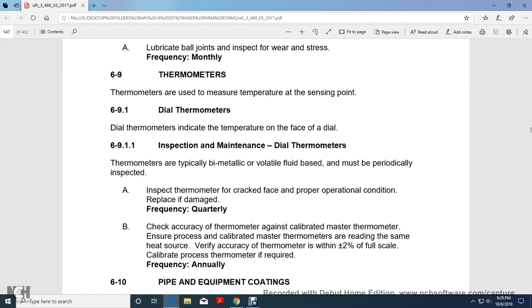Alright, 6.9, thermometer. Thermometers are used to measure the temperature at the sensing point. A dial thermometer indicates the temperature on the face of the dial. Inspection and maintenance of the dial thermometers. Thermometers that are typically bi-metallic or volatile fluid based must be periodically inspected.